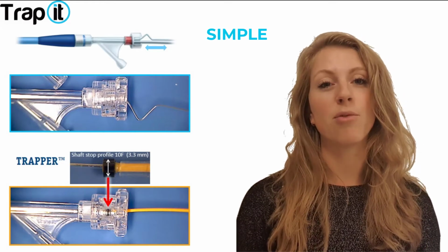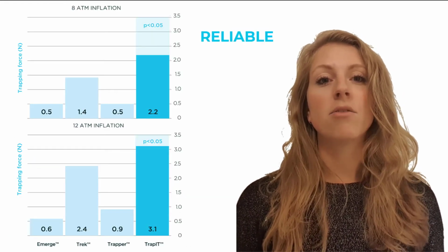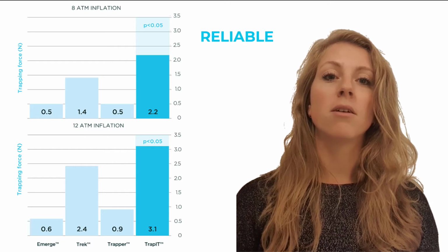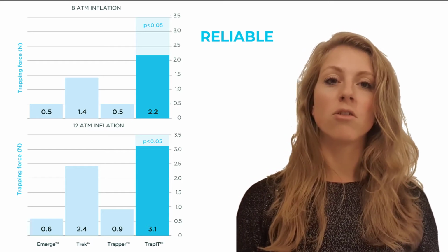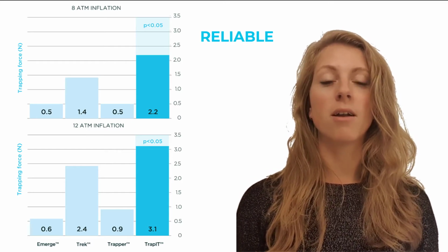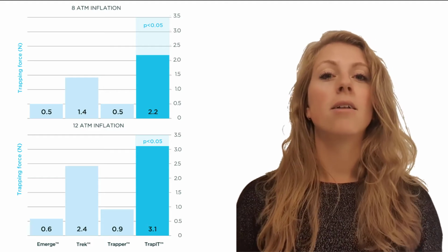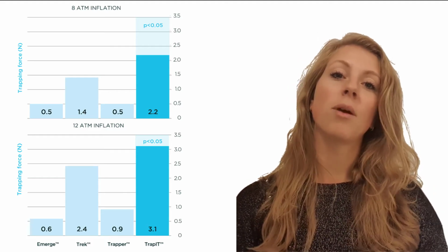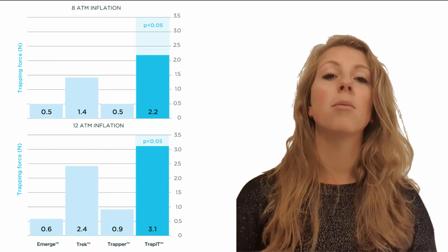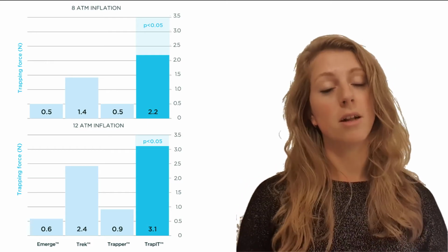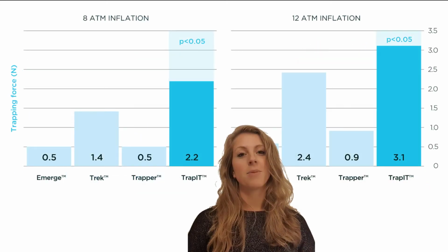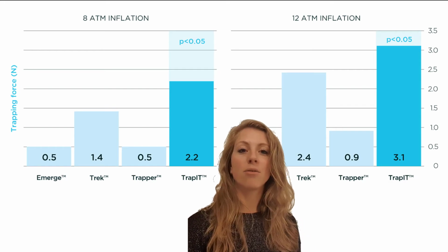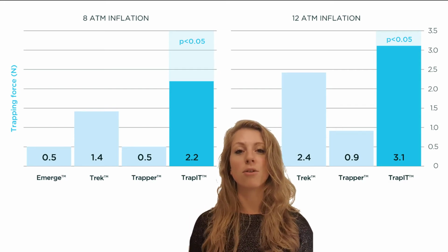Not only the simple autostop design of the TrapIt makes the TrapIt very reliable, but also the high trapping performance. In this test results, you see that we have been testing the trapping forces, so the forces needed to trap guide wire inside the guiding catheter, and the TrapIt is resulting in the highest trapping performance versus other regular balloon catheters, but also versus other dedicated balloon catheters. This is due to the lack of hydrophilic coating and the material of the balloon.